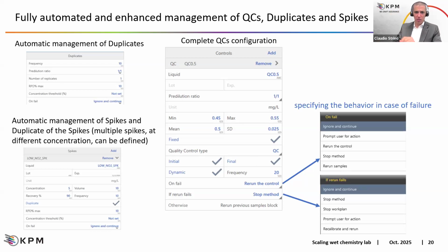Now we saw the corrective action on the R-squared, on the duplicate, on the spike, on QC. And what does it mean? If one of our results does not match the defined acceptance criteria in the software, we can decide, on fail, one of the 5 available actions. For example, rerun the control. Also on rerun fail, we can decide what to do. For example, stop only this method if there is an issue, and go ahead completing the routine with all the other analytes scheduled for all our samples. Otherwise, if the rerun passes, you can just rerun the previous sample block.